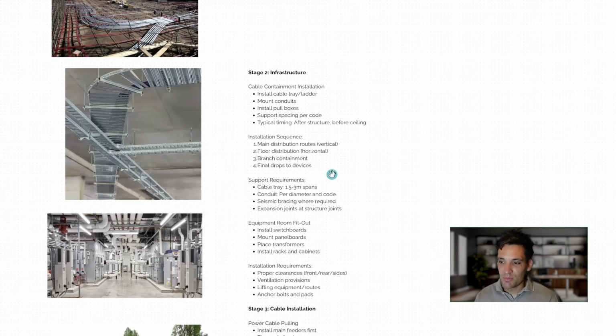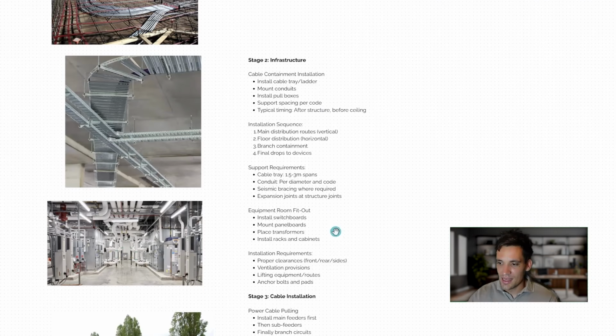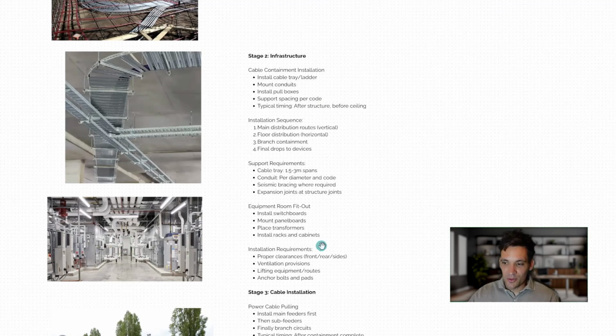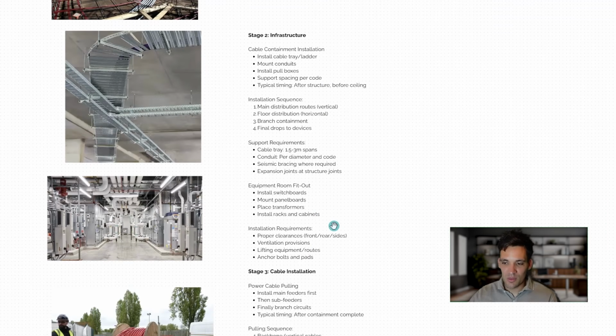Typically, we'd put in our main distribution routes first. So these would be the larger cable trays. At this stage, we'd put in any smaller branch containment and the final drops of devices at the same time as we install the devices. And we'd fit out our equipment rooms. Assuming we have the equipment at this stage in the project, we'd put in all our main switchboards, our distribution boards, any transformers, or all the big equipment within the rooms.